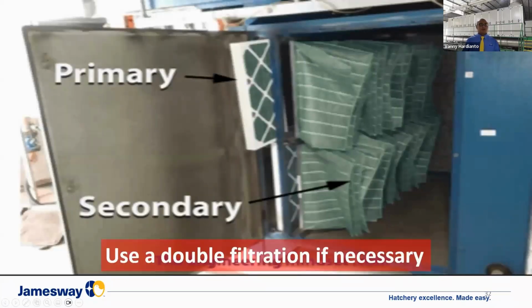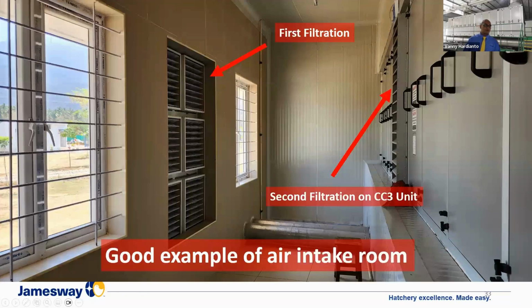Sometimes double filtration will be necessary. In some cases, like in the desert with a lot of dust, you will need double filtration. Here is a good example of using an air intake room before the ventilation unit. The intake room will provide clean air for the ventilation unit because it is equipped with an air filter also.